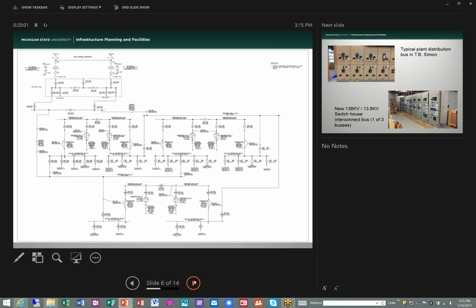You call them dump condensers. Well, we simulate a load, like University of Michigan, we have a 6, I'm not sure, they may have increased it to 10 megawatts, but when we don't have the steam load, we have the electric load, it helps balance it out. It gives you a little bit of a margin. Admittedly it's wasteful in terms of BTUs, but it's more economical. You guys know that trade-off with the cogen plant.